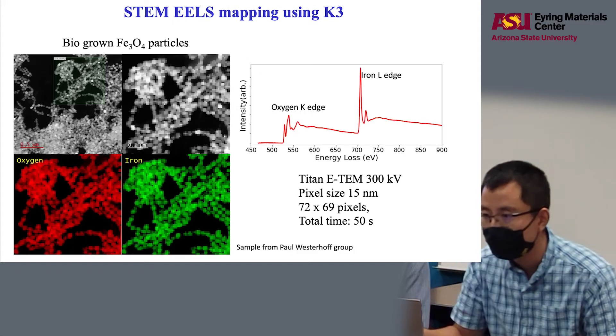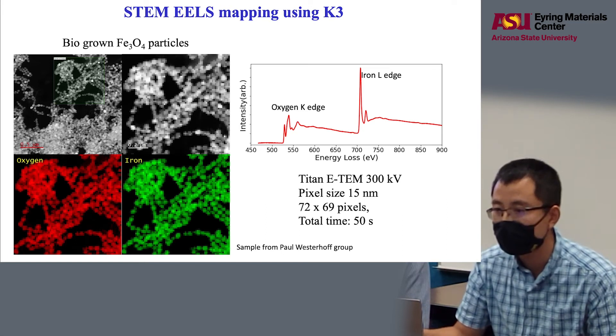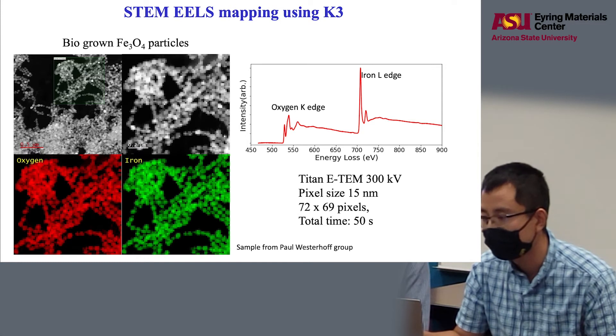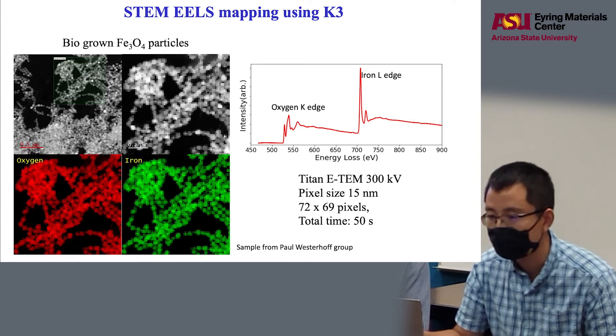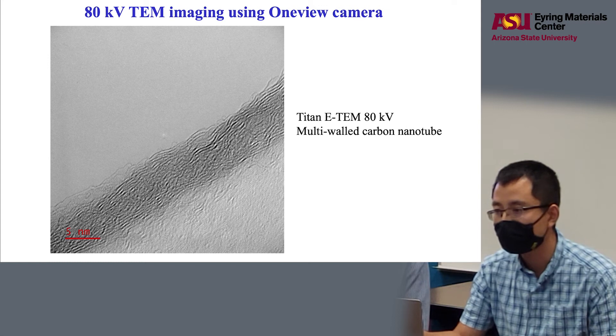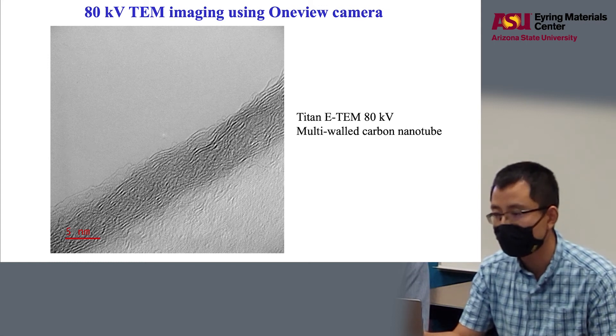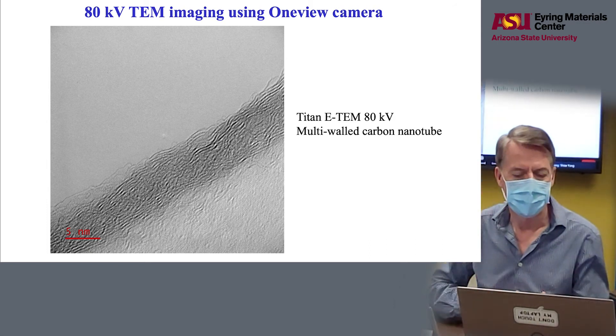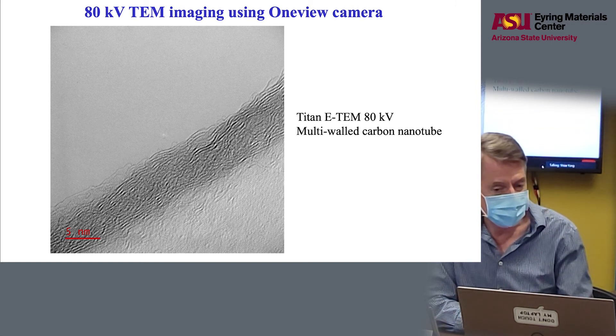Here is another example using the K3 for biogrown iron oxide particles. Here is the typical EELS spectrum of oxygen and iron, and we can quickly get this result within about 50 seconds, showing a beautiful distribution of the elements. Here is another example using 80 kV TEM to image beam-sensitive carbon nanotube materials — we can get atomic resolution with the help of the aberration corrector. For this example, we are not using the K3; we are using the other CMOS camera, which has much better sensitivity at 80 kV but not at 300 kV. That is why we have both sensors.